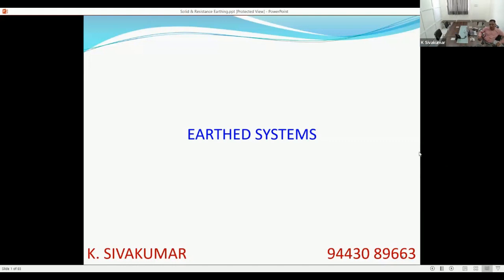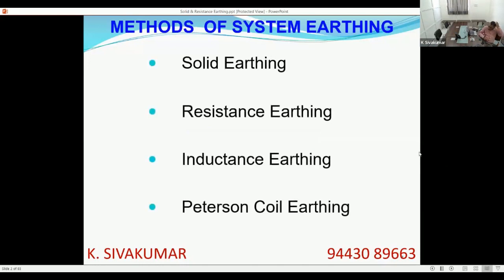So we will proceed with the methods of system earthing. Please remember, we are discussing only system earthing here. System earthing in the sense of earthing of the current carrying conductor, that is mostly the neutral of the transformer, the neutral of the generator. There are 4 methods of system earthing practiced: solid earthing, resistance earthing, reactance earthing, which is normally called inductance earthing or reactance earthing, and Peterson coil earthing. We will discuss one by one. Maybe in this session we will have solid and resistance. Maybe in an upcoming session we will discuss the other 2.